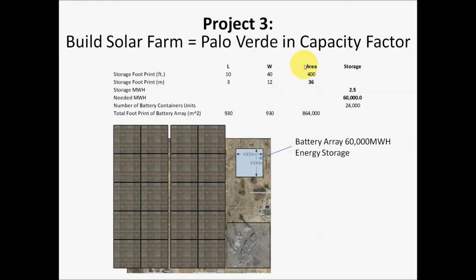Dividing our 60,000 megawatt hours by the 2.5 megawatt hours each battery unit stores, we'll need 24,000 of these battery units. With each unit's known footprint area, I calculated the total footprint, rounding up since we'll need extra space for entryways and access to the battery bank storage. I estimated roughly a 1,000 by 1,000 meter area will be effective for our battery array.